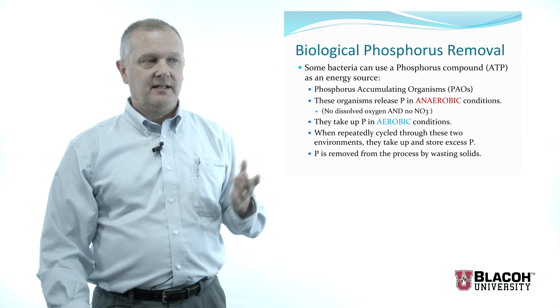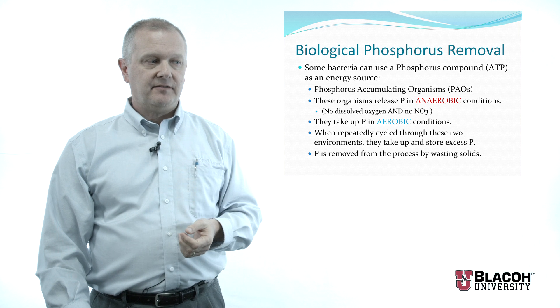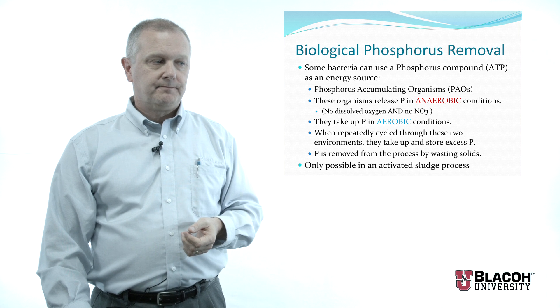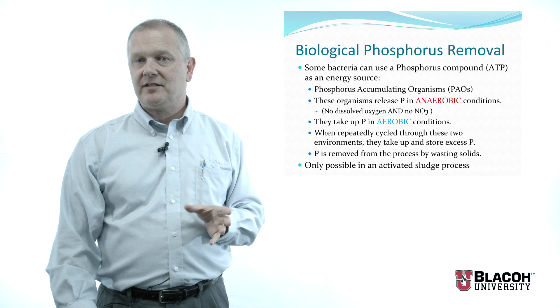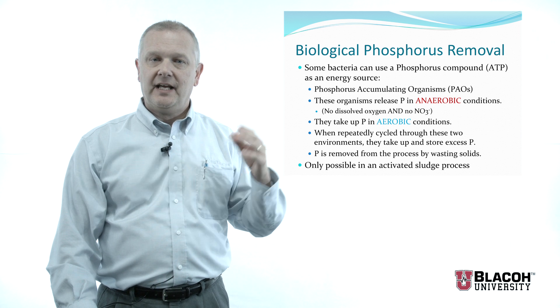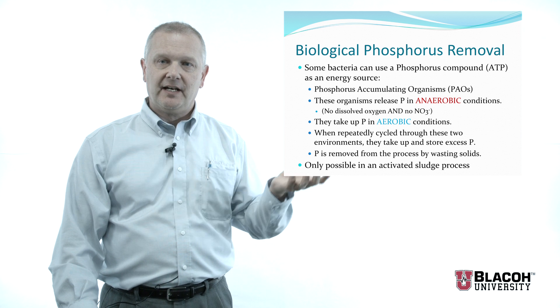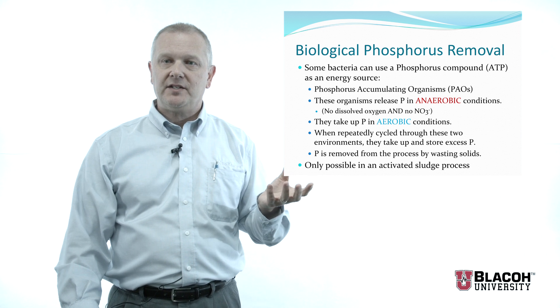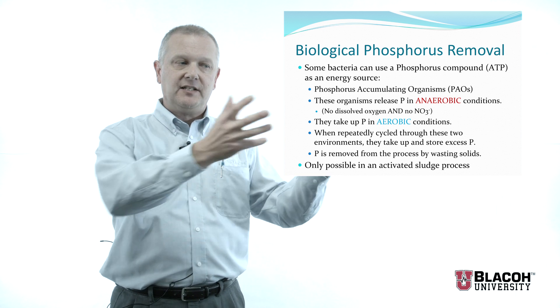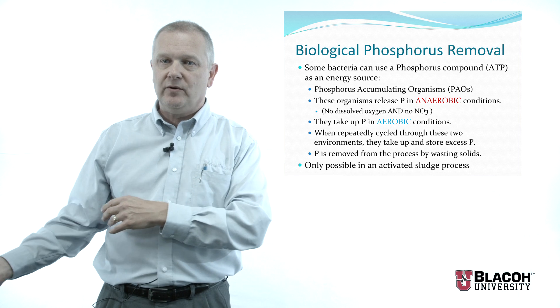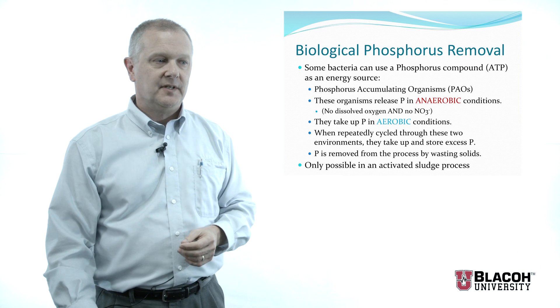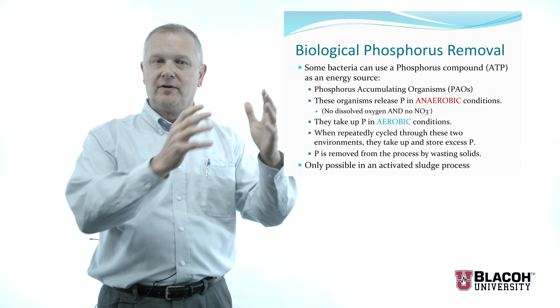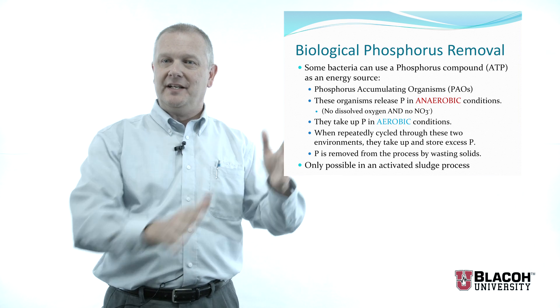This biological process is very effective, but it's only possible in an activated sludge process. We can't do this in any kind of fixed film process because we have to physically remove the organisms from the system, and you can't do that if they are growing on a fixed media.